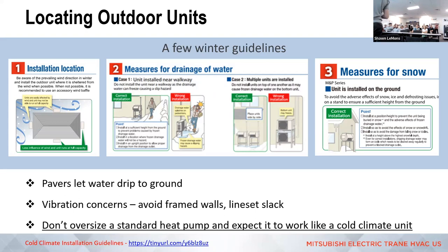That said, these units are tested in a gigantic freezer back in Atlanta, and there's no sun in the freezer, so they do the job without any extra help—just testing their raw capabilities. But if you can get the outdoor unit located where it sees a little winter sun, that sun can help manage defrost, capturing free energy instead of spending it on your utility bill. You'll get a little less noise, less defrost cycling, and more heat delivered.